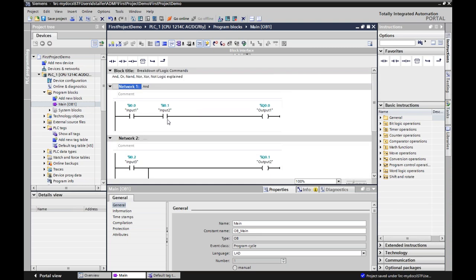This is a basic setup for programming. Right now, this is what we would consider AND logic — it uses examine on. In ladder logic, you're used to seeing a normally open contact and a normally closed contact. A normally open contact means when unenergized, no power passes through. A normally closed contact means power is passing through, and when actuated, power stops. With a PLC, it can't see the state of the switches — it only sees the state of power being present at the terminal block.